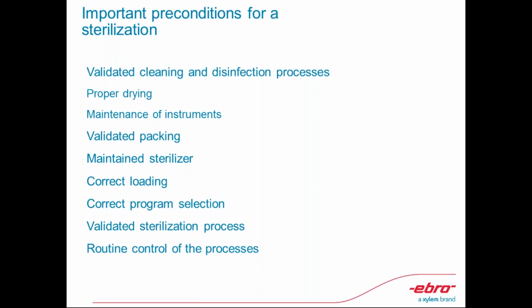Okay, the important preconditions for a sterilization. As we mentioned a while ago, cleaning and disinfection processes must be validated. Why? Because it's hardly possible for an object or material that is not clean to be sterilized. Then the proper drying, maintenance of instruments, the packaging, and a maintained sterilizer.